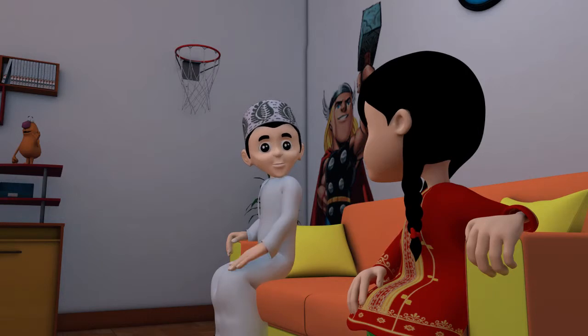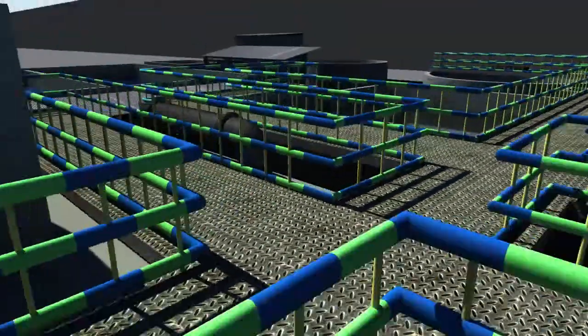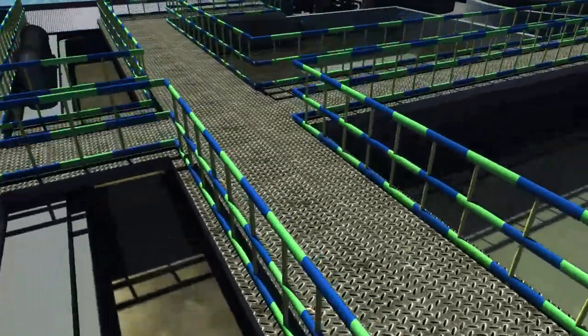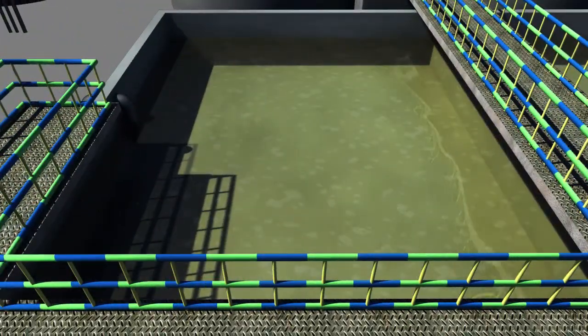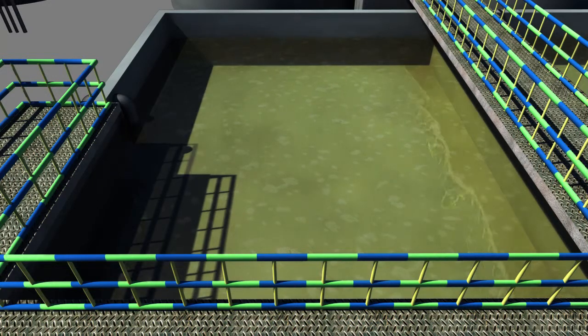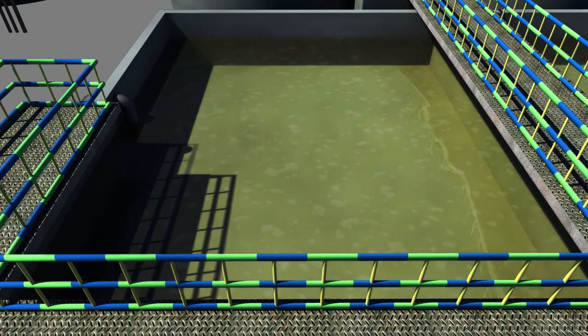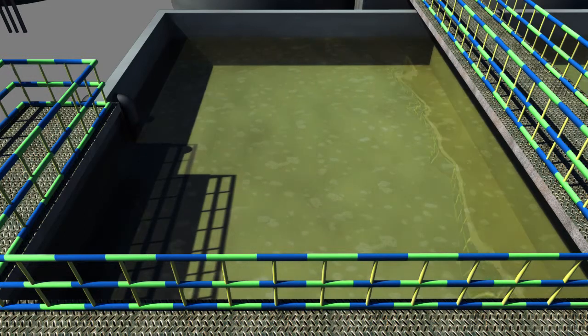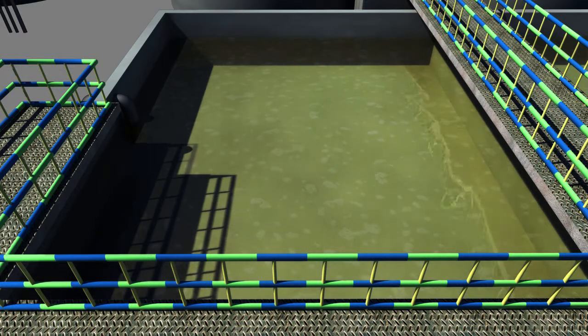Is the wastewater clean now? Of course not — there's more cleaning to do. This is interesting! Now that the wastewater is cleared from solid elements and grease, it's time to clear it from bacteria, and so it moves into the biological treatment tank. Here, very tiny bugs do the job of cleaning the wastewater from bacteria by eating them. These tiny bugs — too small to be seen with the naked eye — clean wastewater by eating the waste and converting it to nitrogen gas, carbon dioxide, and other gases. They do this continuously, and we need to supply them with air to survive. That is why air blowers are used in the biological treatment tank.